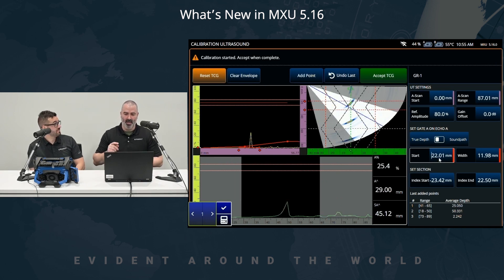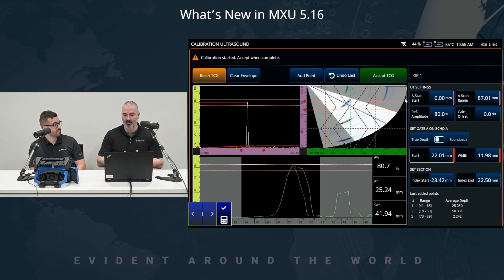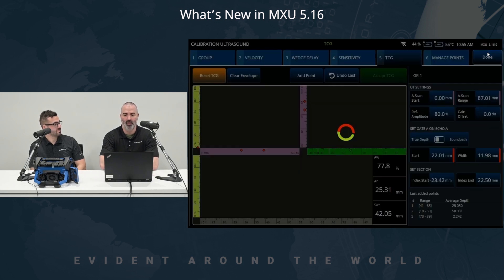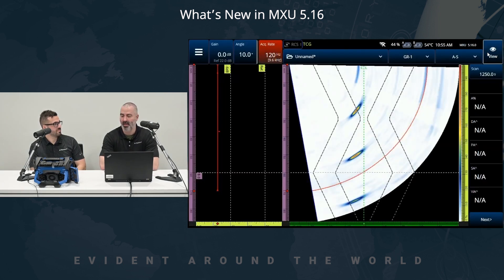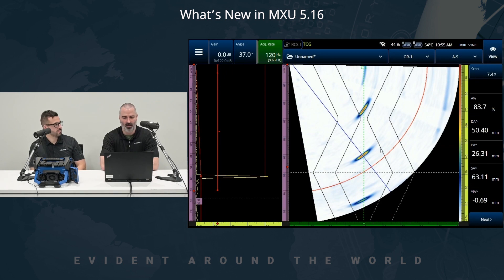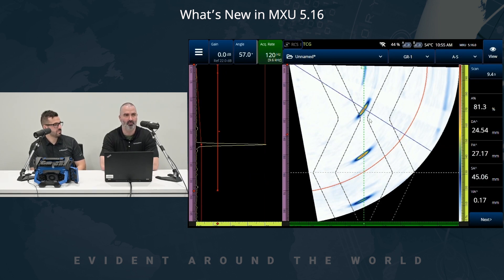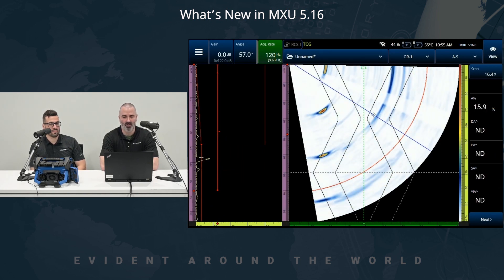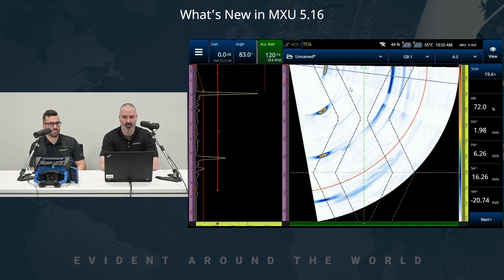As you can see in the bottom right, we have our three points that were added. Regardless of whether they were added from shallowest to deepest or in any order, they get added correctly. Going back live on screen, we can validate that we still have our reference levels with the TCG curve for side drill hole number one, number two, and moving the probe back to revalidate the notch in the HAZ, we are still on point there as well.